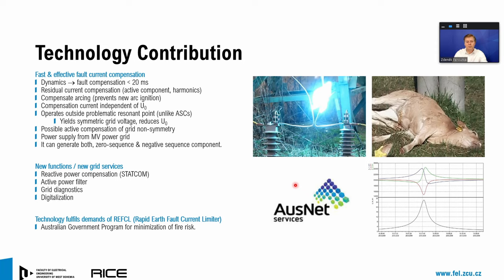The technology contribution. With our idea and our device, we offer very fast and effective fault current compensation. Dynamics is excellent. The fault is compensated below 20 milliseconds. We are able to secure full zero residual current. It means that we are able to fully compensate the fault current, including the active fault current component as well as higher harmonics in the fault current. We are able to compensate the arcing, and by special control interventions, we are able to prevent new arc ignitions.